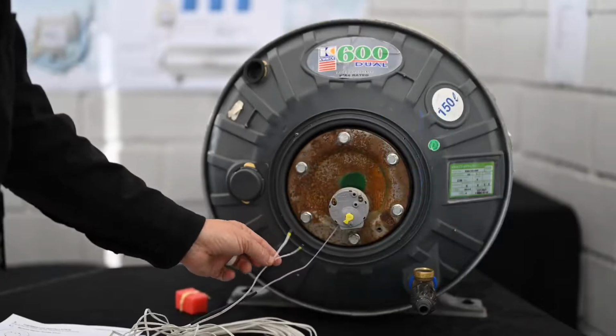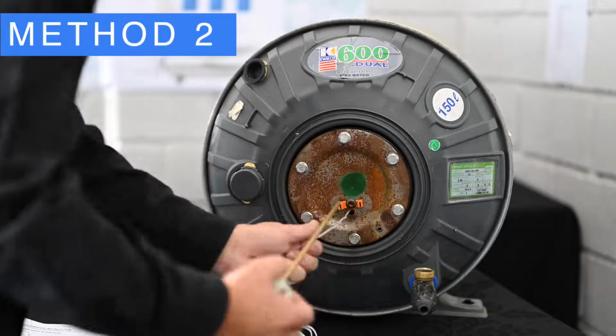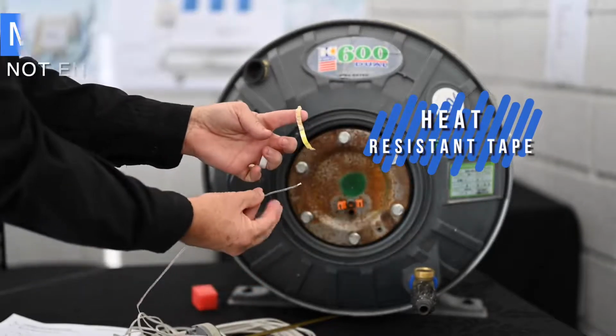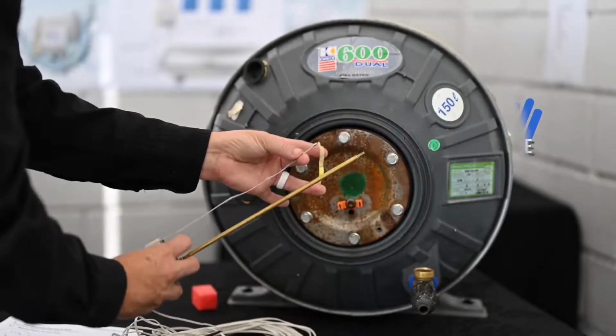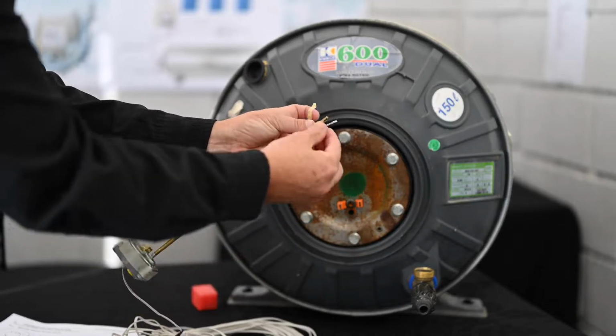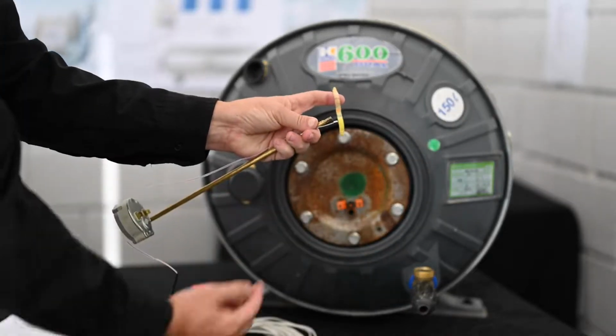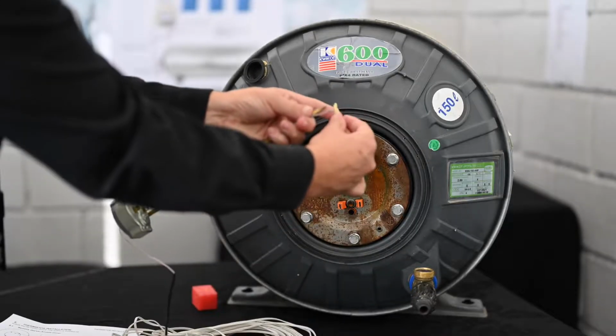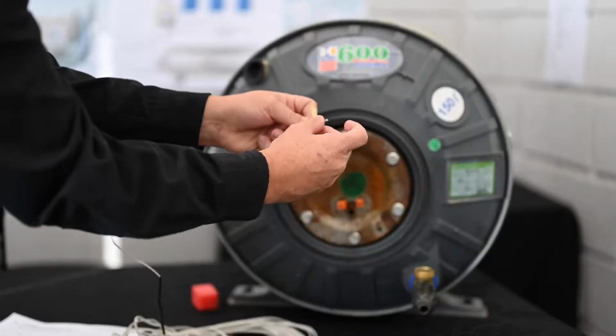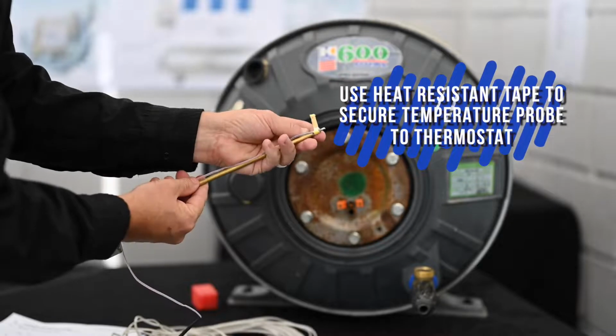But you might not have enough roof space, and it might be a bit difficult to install. So another way of doing it is we supply you with a bit of heat resistant tape. And one thing you can do, a little bit tricky, but if you do it on the ground and not in the roof, it's much easier, is to make sure the probe is just sticking beyond the end of the thermostat, and then use this tape to secure the temperature probe. So there we go, we can see the temperature probe sticking beyond the end.